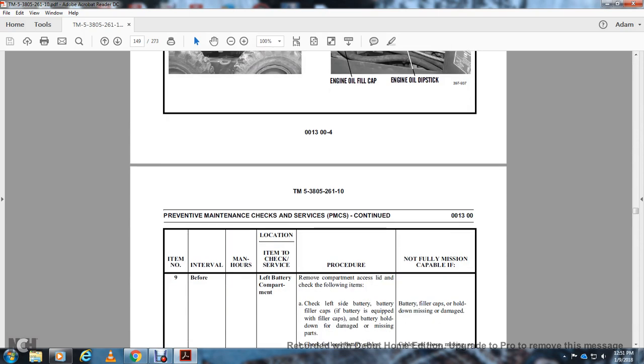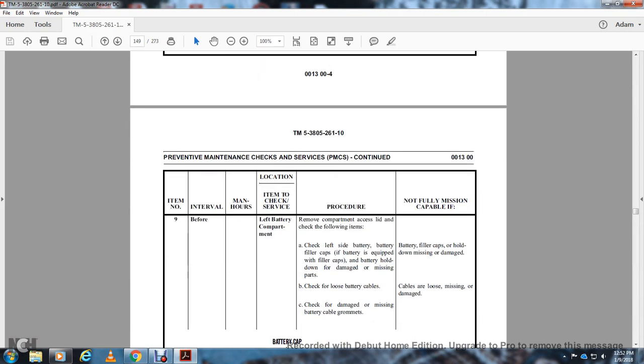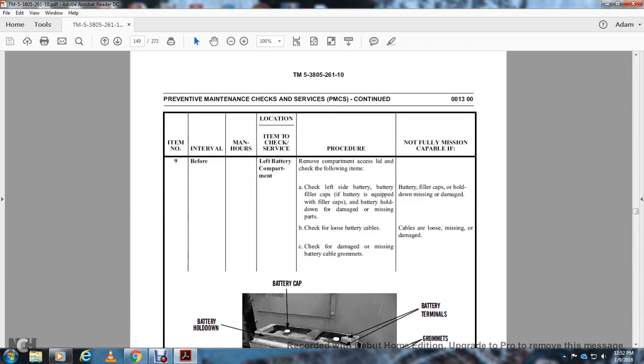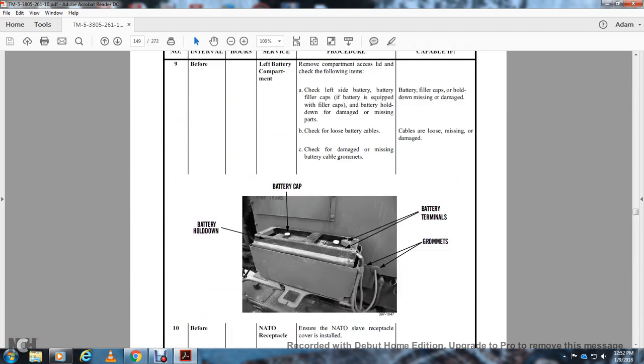Then remove the compartment access lid. Check the following items. Check the left side of the battery filler caps, if the battery is equipped with filler caps. Check battery hold down for damage or missing parts. Check battery filler caps and hold down for missing or damage. Check for loose or damaged cable. Check cable for loose, missing, or damage. Check for damaged or missing battery cable grommets. This shows the battery hold down, the battery cable, and the battery terminals of the grommet.